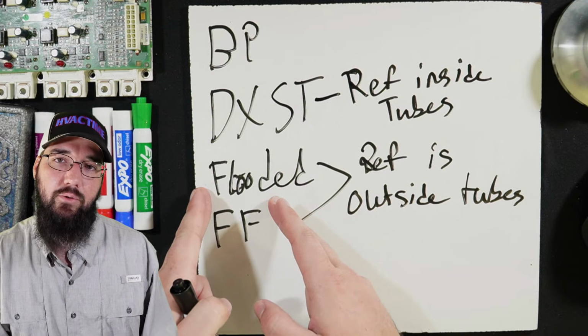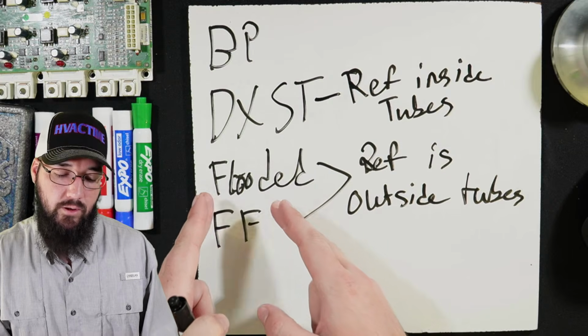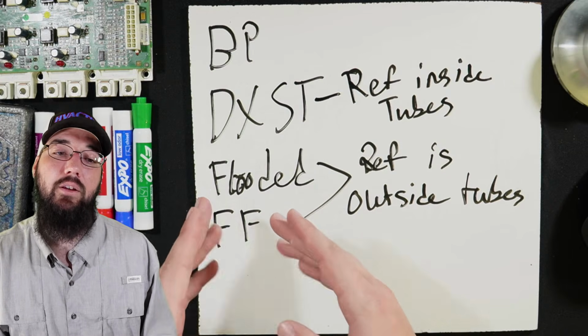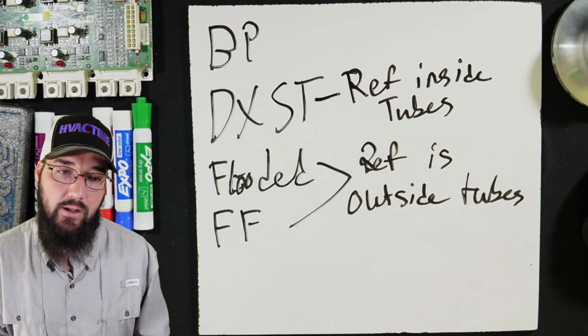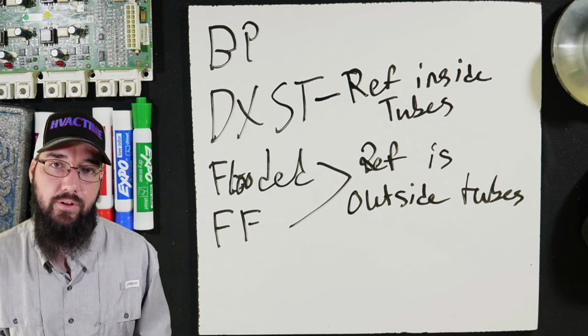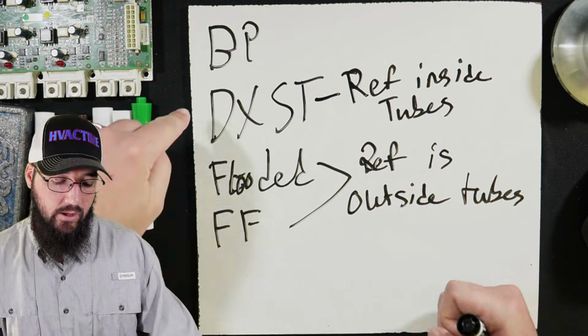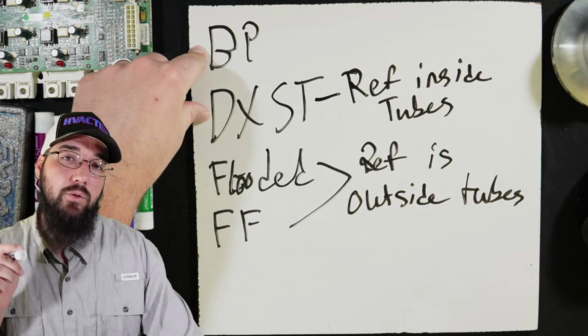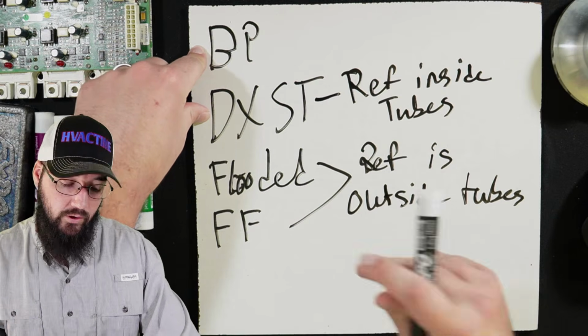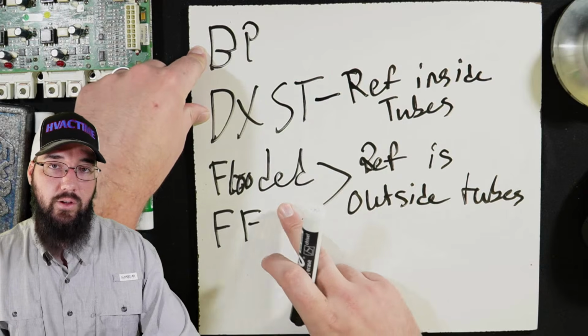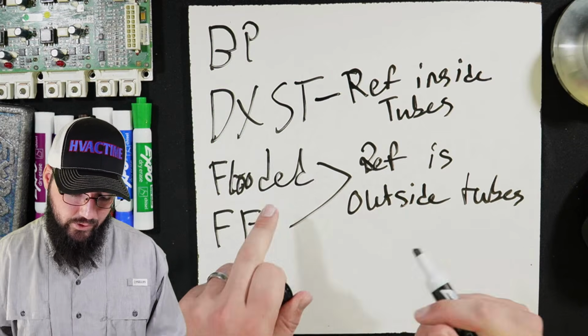If we can get to the liquid refrigerant here, then doing the push-pull or pull-pull method works, because then we can directly get all of that liquid refrigerant out of there very rapidly. When we start dealing with these two, which is what the majority of air-cooled machines are. Now, there's a lot of machines that do use these, okay? So I'll give some examples that use a flooded.